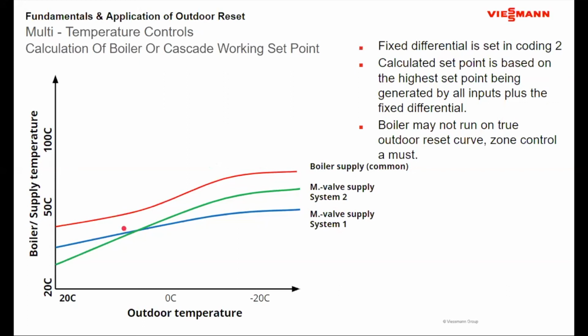When we start to look at the temperatures that the boiler is operating for its outlet temperature, the thing to remember, from the aspect of outdoor reset control, particularly with the higher level controls, is there's a lot of things going on in the background that's driving that boiler water temperature. The end result is if you're looking at the water temperature, the boiler may not be operating off of the outdoor temperature you're expecting it to see because of the other requirements of the boiler to make sure that it's meeting all the demands of the loads on it.